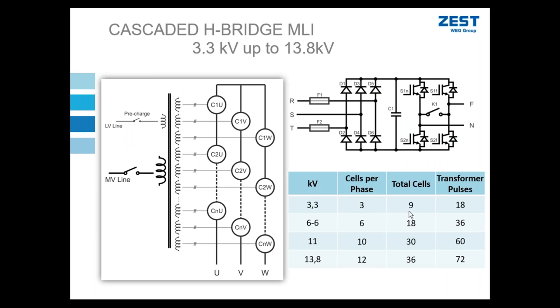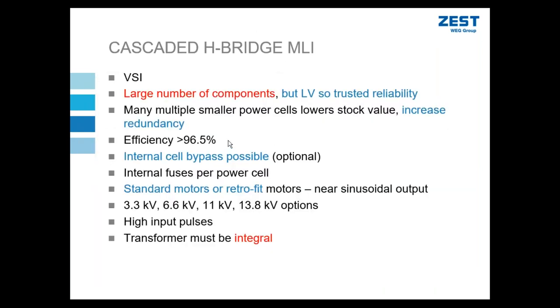Now I've got to put in a minimum of 9 for a 3.3 kV solution. I've got to put in a minimum of 9 power cells. In my NPC topology, I only needed 3 power cells. So it adds a lot of components. This does decrease the efficiency of this topology. But the low voltage IGBTs have been used for a long time, and so there's some robustness because of the IGBTs that are used.